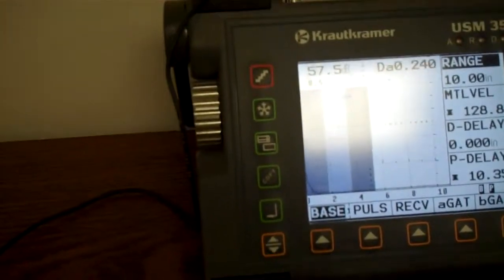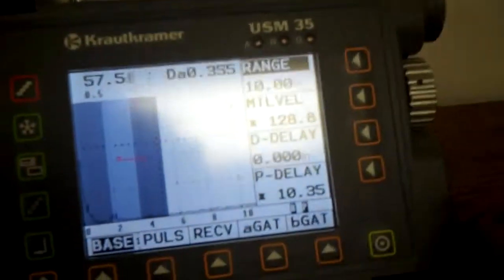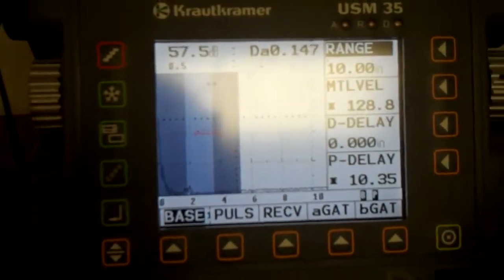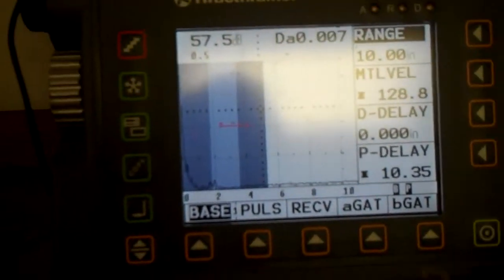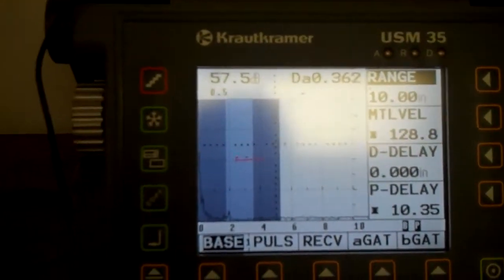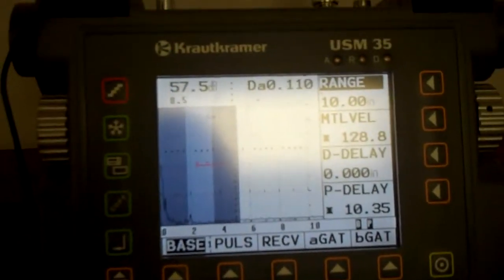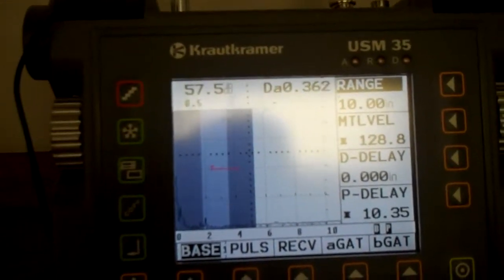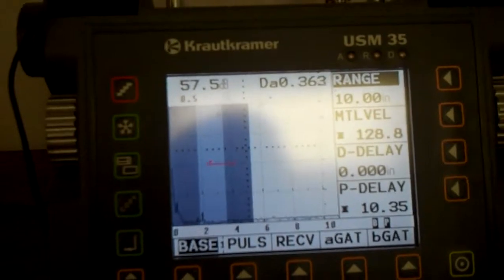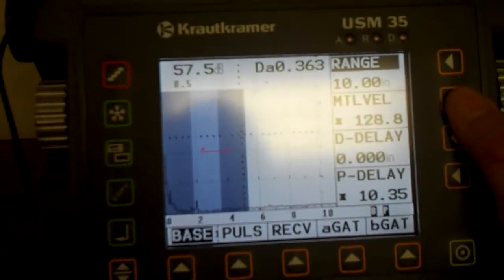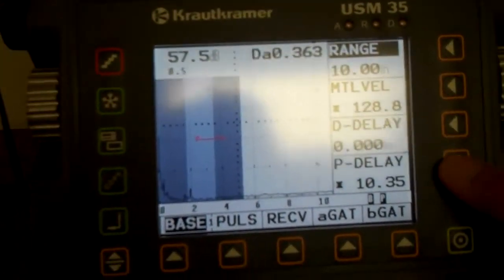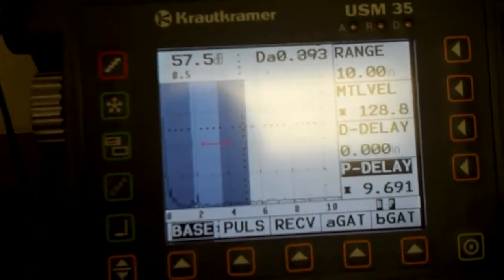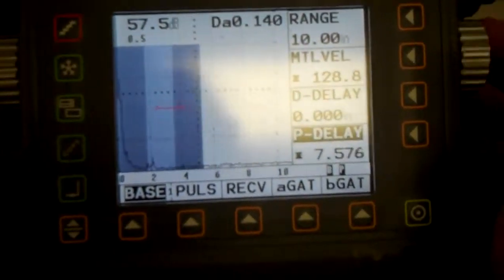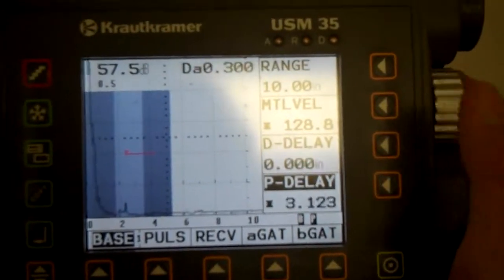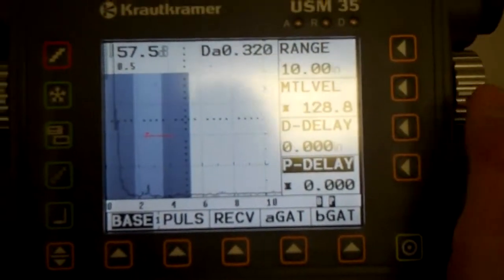70-degree transducer there. So all we're looking to do to start with is just, as we have before, match the probe to, or I should say transducer, to the scope. So using a USM 35 scope here, I'm going to take this thing, and right now 10 inches screen range is totally fine. All I did was turn this thing on. Material velocity 0.128, that should get us a good starting point. For kicks and grins, we're going to roll this delay back down to 0. I always like to start at 0. That's probably the best place to go with it.